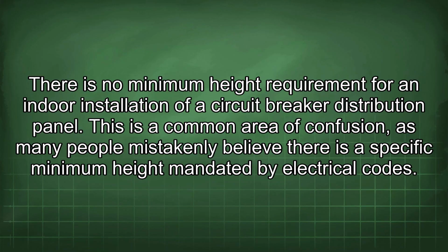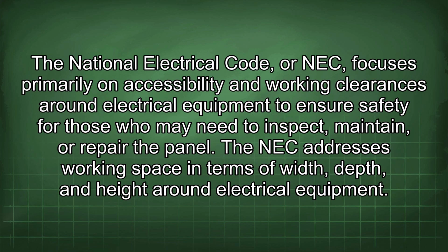There is no minimum height requirement for an indoor installation of a circuit breaker distribution panel. This is a common area of confusion, as many people mistakenly believe there is a specific minimum height mandated by electrical codes. The National Electrical Code, or NEC, focuses primarily on accessibility and working clearances around electrical equipment to ensure safety for those who may need to inspect, maintain, or repair the panel.